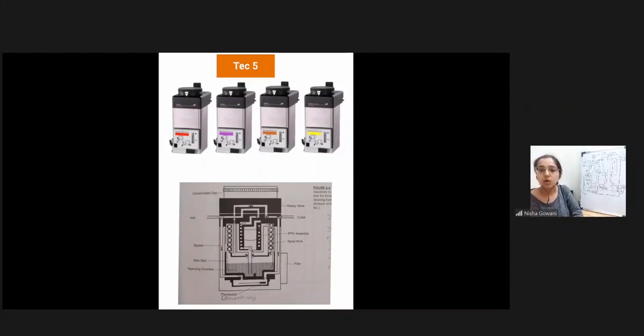Above, we can see the structure of the vaporizer externally, and below we can see the internal structure of the vaporizer. All these vaporizers which I'm going to show you are variable bypass vaporizers and they're temperature compensated. That's why the name Tec has come, because of temperature compensation. You can see this vaporizer has all the parts which I have drawn in this schematic diagram on the board.